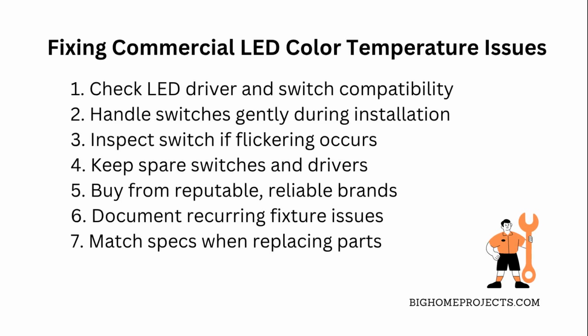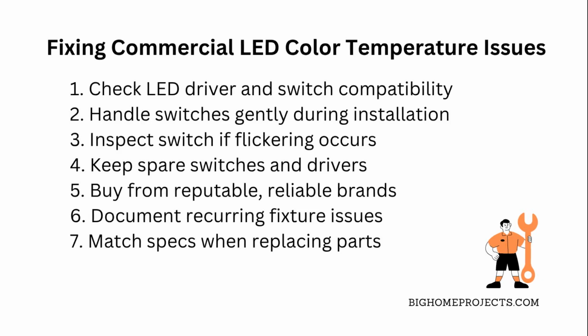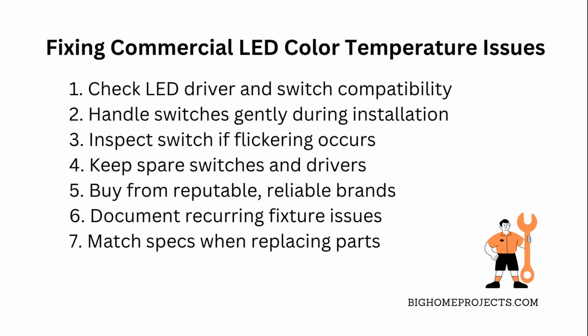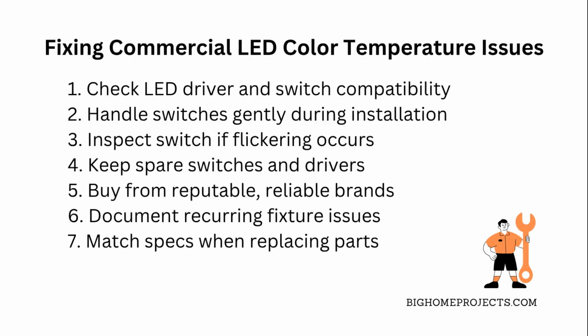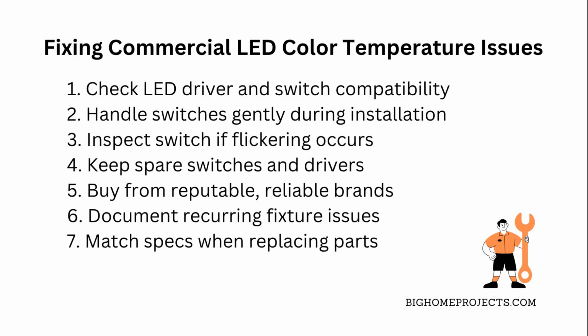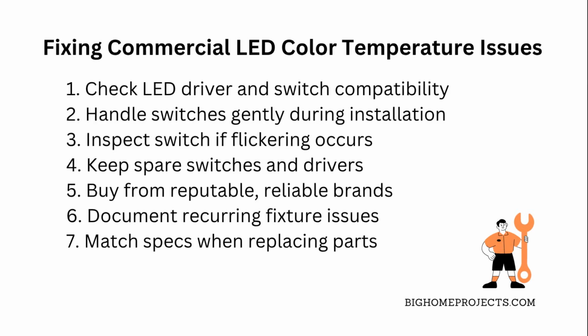First off, always check if the LED driver is compatible with the color temp switch, because cheap combos are usually a disaster waiting to happen. When installing, handle the switches gently. Too much force or twisting can wreck them early. If you spot flickering or inconsistent color temps, that's a red flag to inspect the switch and driver immediately. It helps to keep spare switches and drivers on hand so you're not scrambling when one goes bad.